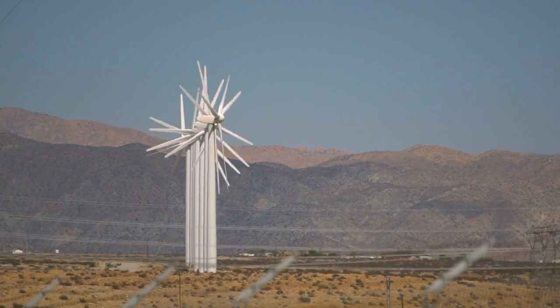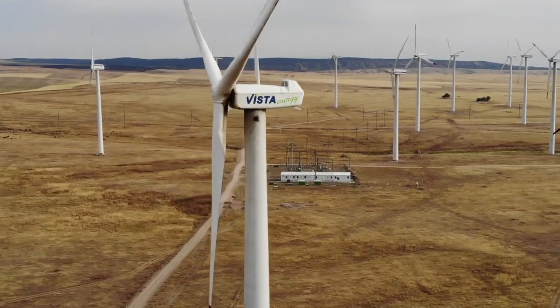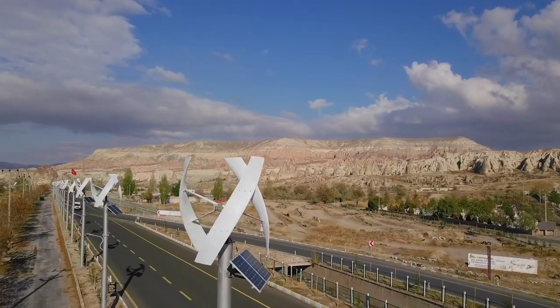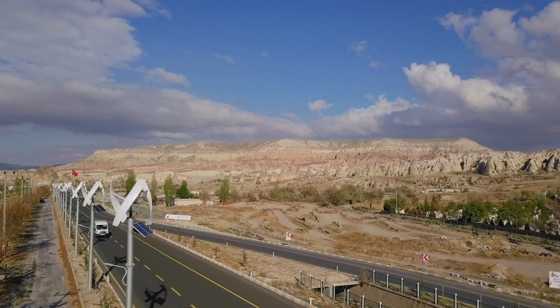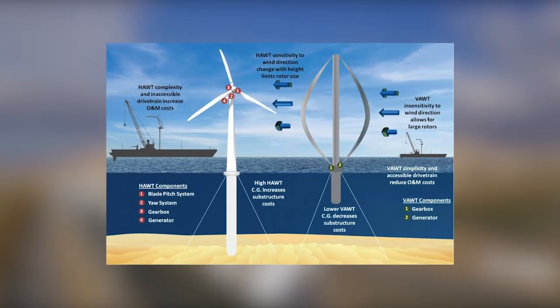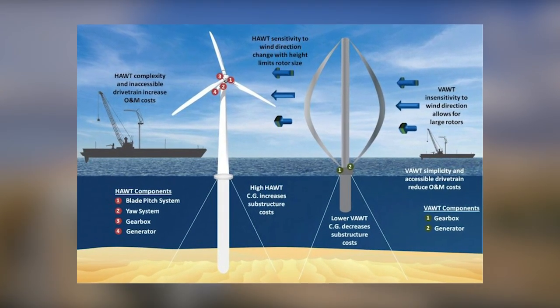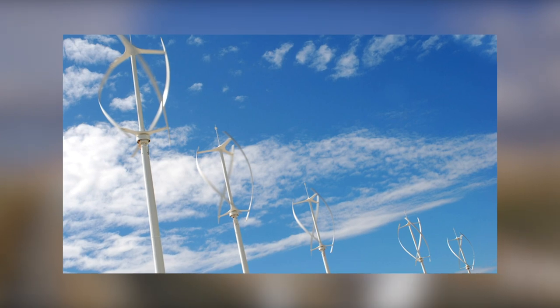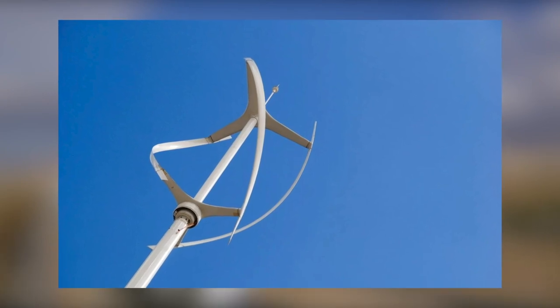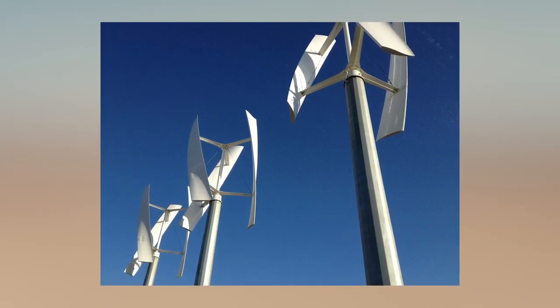Pretty much all of the wind turbines that we see dotted around these days are HAWTs, whether they're offshore or onshore. This means that the centre of the rotor and the shaft that it rotates is horizontal, making it parallel with the direction of the wind. Now the vertical axis wind turbines, or VAWTs, flip that on its side quite literally, with the main rotor shaft arranged vertically so that it's perpendicular to the direction of the wind. A major advantage of this arrangement is that the turbine doesn't need to be pointed into the wind to be effective, as VAWTs can utilise winds from varying directions. With the vertical axis, both the generator and gearbox can be located closer to the ground at the base of the turbine, making it more accessible for maintenance and repairs, as opposed to climbing all the way to the top of a HAWT.